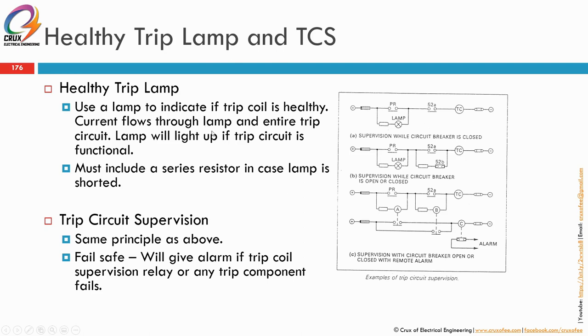So the healthy trip lamp uses a lamp to indicate if the trip coil is healthy. Current flows through the lamp and the entire trip circuit. The lamp will light up if the trip circuit is functional. So if you look here, this is the protection relay. This is the breaker status. This is the link, this is the fuse.